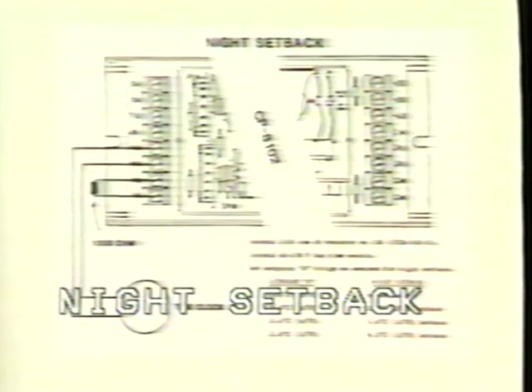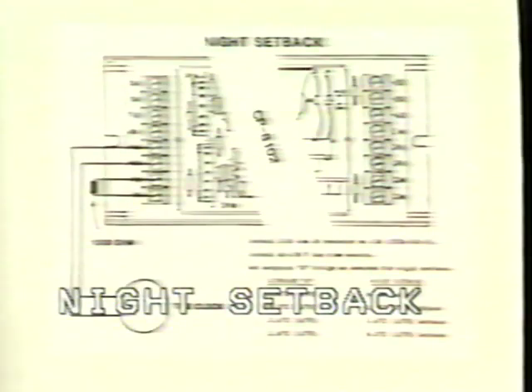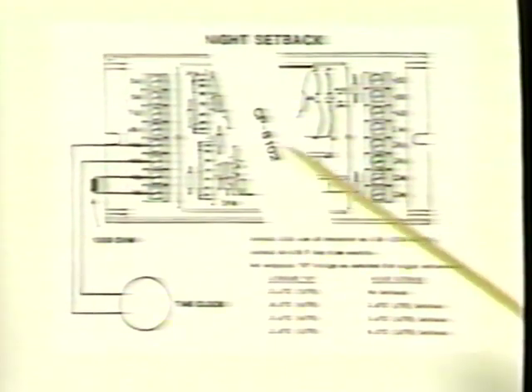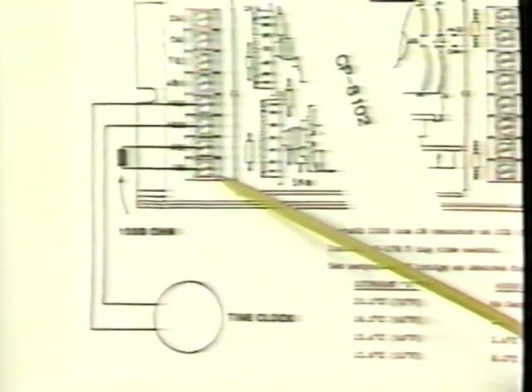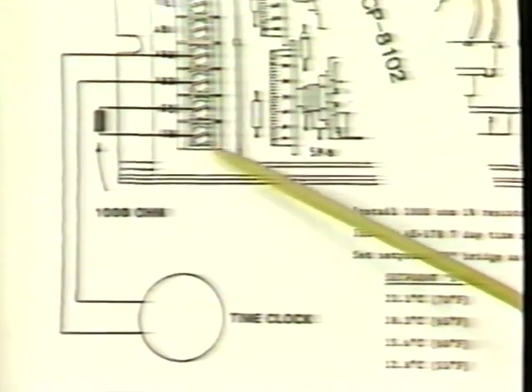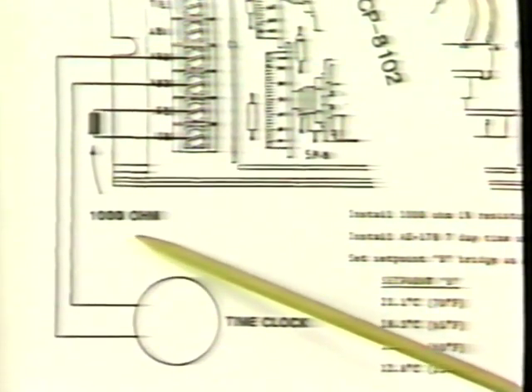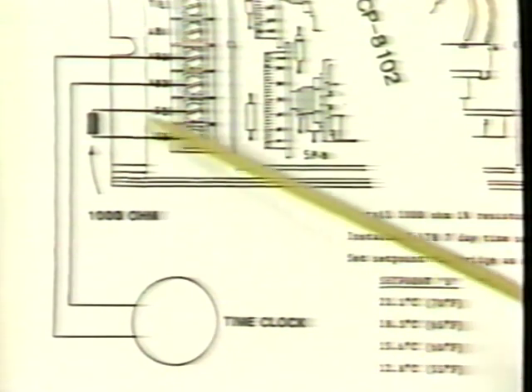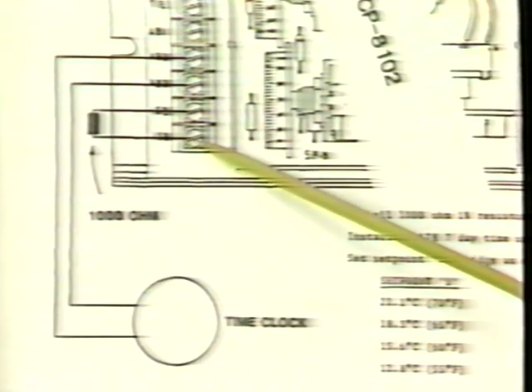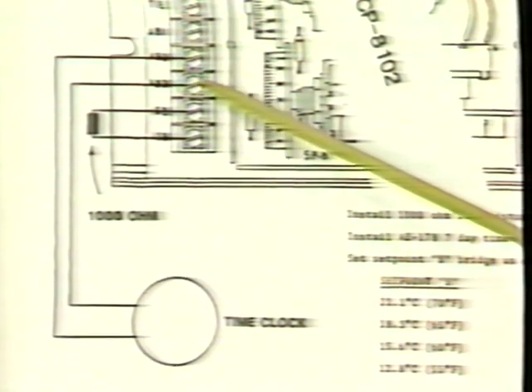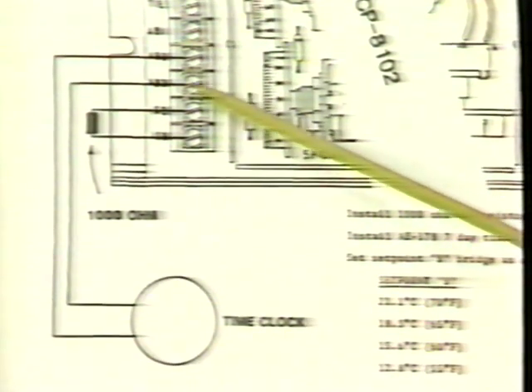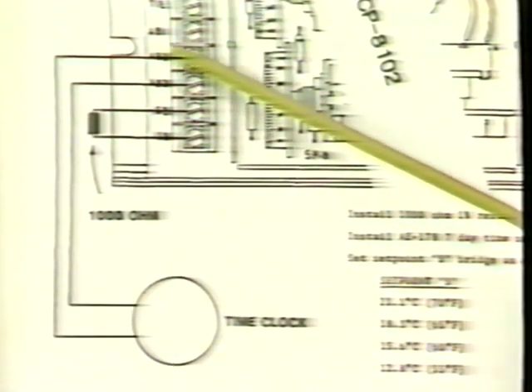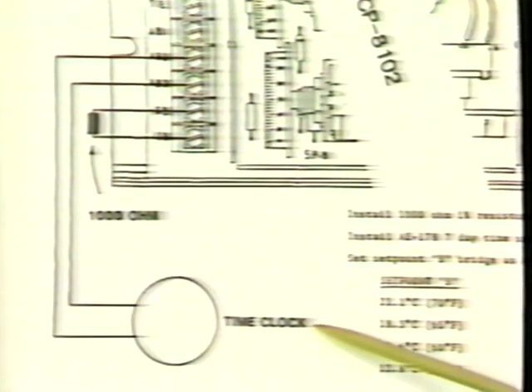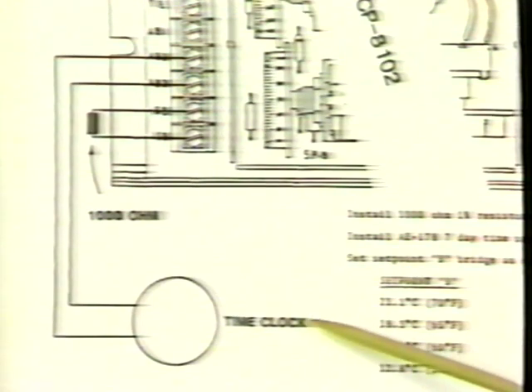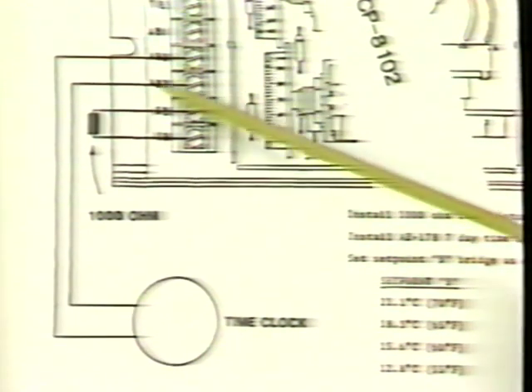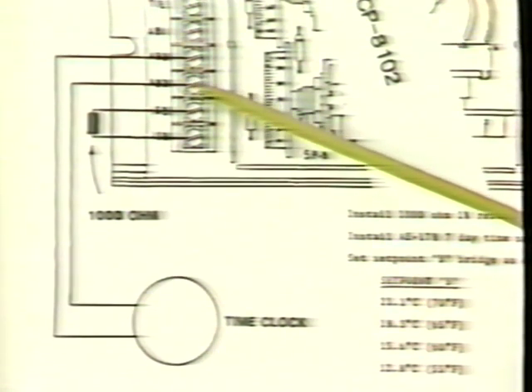This diagram illustrates the option of adjustable night setback. It can be used whenever the B input of the CP8102 is not required for reset. A 1,000 ohm plus or minus 1% fixed resistor is installed across terminals ISB. The jumper normally installed between AB2 and AB3 has been replaced with leads going to some sort of mechanical or electronic time clock. That clock will close contact, completing this bridge when we want the setback.